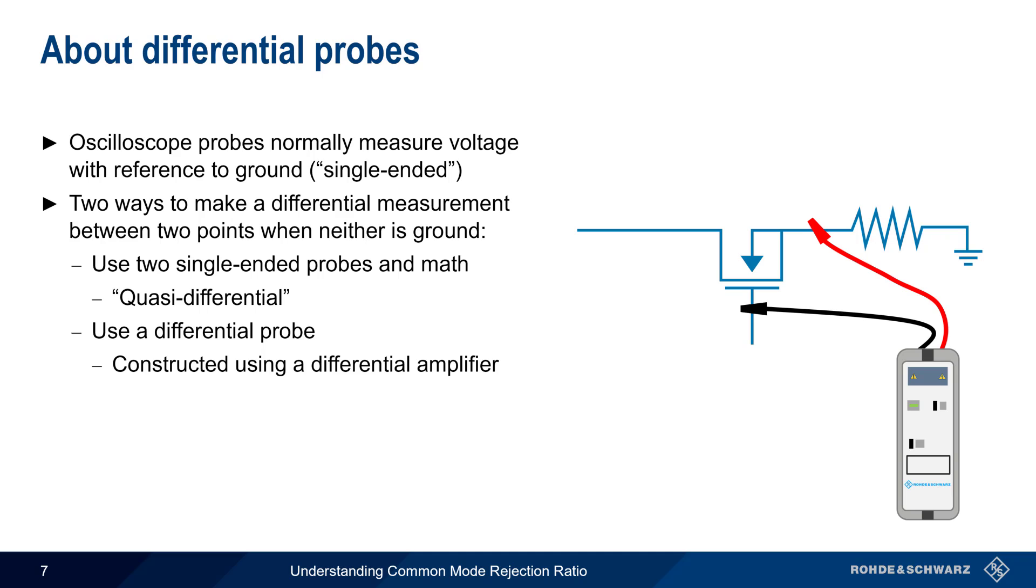There are many reasons why differential probes are superior to the quasi-differential approach. And one of these reasons is that a proper differential probe has a much better common mode rejection ratio than can be achieved in the quasi-differential approach.